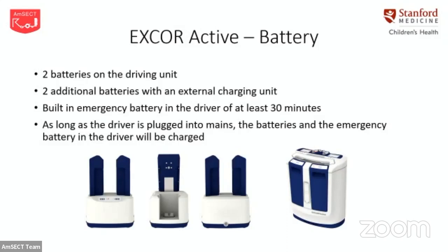And when I say there's a minimum of 5 to 6 hours or a minimum of 30 minutes on these batteries, really it depends on your pump size and rate that you're using, the pressures that you're using. So the battery time can be longer than that, but a minimum of 5 to 6 hours, or 30 minutes with the emergency battery.